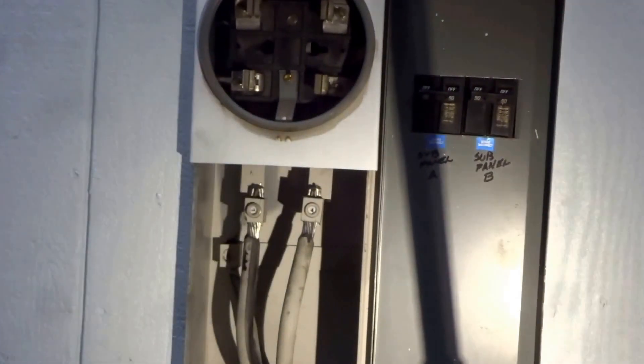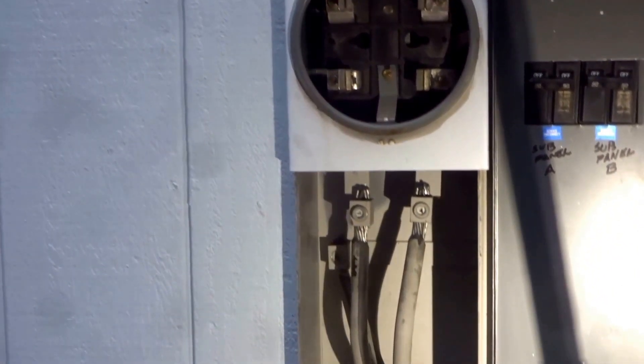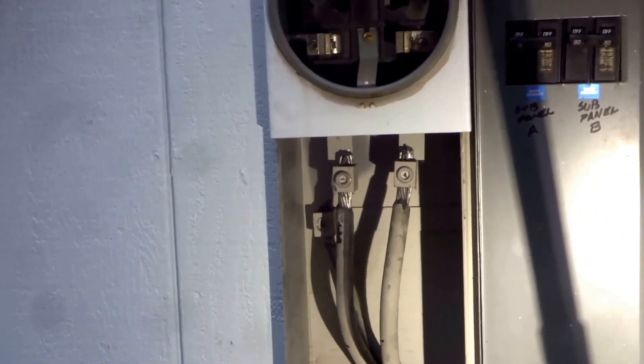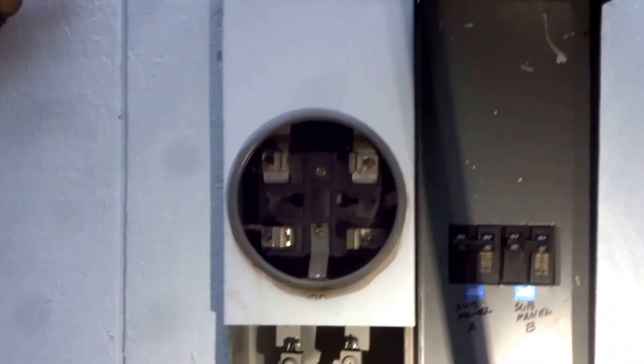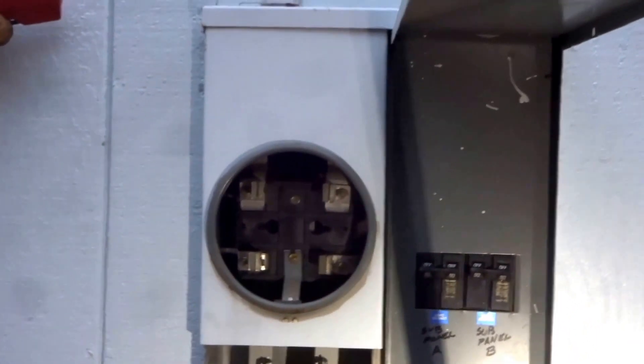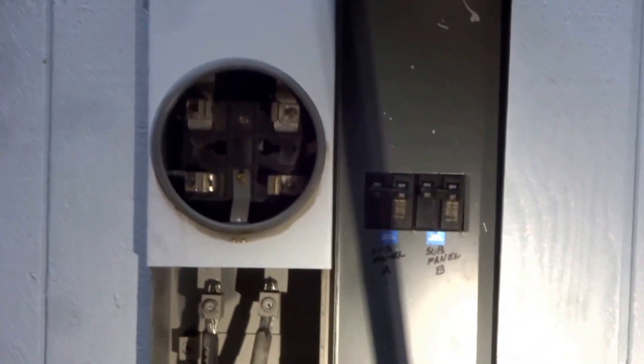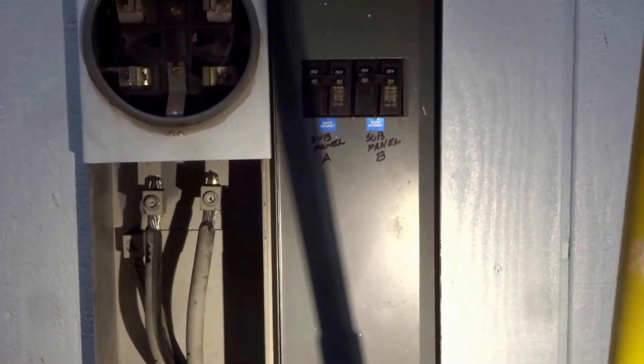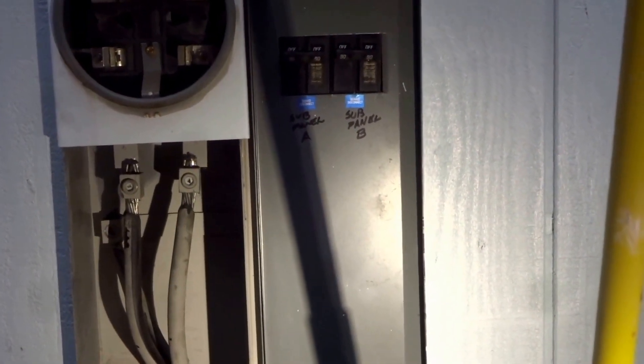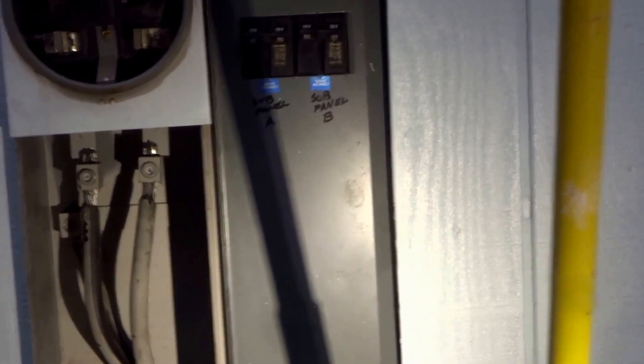When we're doing our testing for these kinds of purposes, we sometimes find four or five amps going to ground. And just tightening up the neutrals helps. Sure. And I tried to tighten that one, but I don't want to yard on that anymore cause I'm going to break it. Is the screw stuck in the block? How about some WD 40 or penetrating? I don't have a solid base there. This is only tack tacked on here.